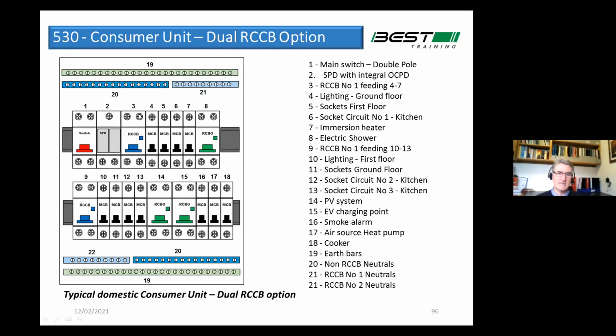So as a minimum, you've got to have 2 RCCBs in the board. And typically the way you do it, maybe the ground floor sockets and the upstairs lights would be on the same RCCB, so that if the ground floor lights tripped out, your ground floor sockets will still be okay. So you just plug in a few standard lamps or whatever, and vice versa upstairs. If the lights go upstairs, you can plug in a few table lamps because the sockets are still running.